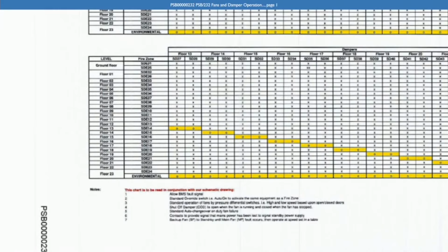Now, I just want to ask you some more detailed questions about this cause and effect chart. Do you agree that this cause and effect chart doesn't state what device causes the activation of the fire zone? You said that this shows you what happens when the smoke control system's been activated. It does. It tells you which smoke detector activates it on the extreme left-hand side. Just show me where you're looking. If we go to the extreme left-hand side, and go up to the upper sheet, it says it on both, basically, SDE01. Then it says 26, then 25, whatever. And those are the smoke detectors in each of the lobbies, are they? Yes.